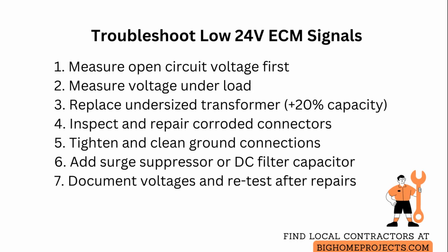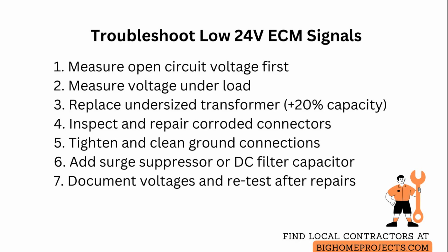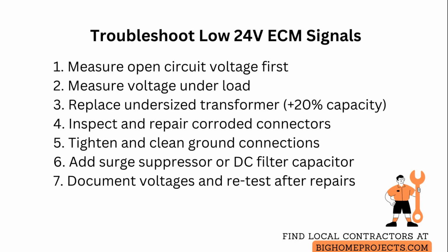range. If the voltage drops more than 2 volts under expected operating load, the transformer is likely undersized and should be replaced with one rated for the full running current plus a 20% buffer.